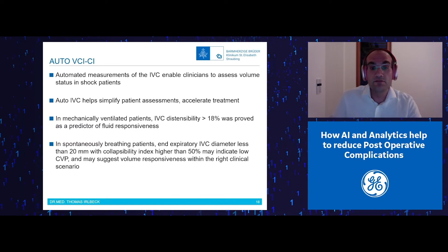I present to you now a video. This is performed on a GE Venue Go. A low frequency phased array or curvilinear transducer is placed in the subxiphoid location. And when you look at the image, you see that it's 2 centimeters away from the right atrium. So the system searches for the appropriate place to measure minimum and maximum diameter during the breathing cycle. And then yellow labeled means that the results should be taken with caution. And if it's marked or highlighted in green, then this shows perfect match with the measurements of an expert.